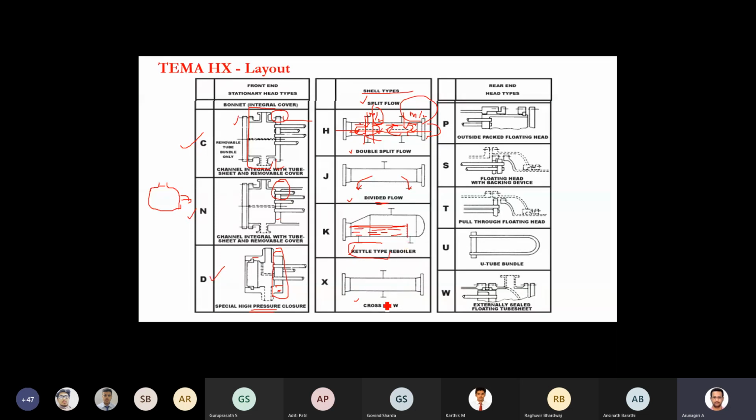Okay, this is your baffle. Here you have a heater arrangement, or you may have U-tube arrangements, whatever it may be. So the fluid will be heated up, then it will go up here. This is your flow in. Once it's filled up, it is being heated. Then you have to provide suitable space between the shell and the liquid surface for disengagement of the vapors which move away from the reboiler. The design of the kettle type reboiler we will discuss in detail in heat exchangers with phase change.